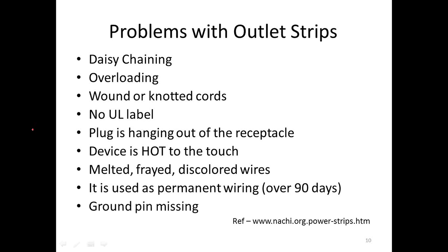Melted, frayed, or discolored wires. Nobody is looking at these things, so they're usually laying on the floor. People walk on them, step on them, put the legs of tables on them, tear them up in all sorts of ways, and nobody is assigned to be vigilant over them to correct problems. They do get used as permanent wiring—we all know once they're in, they're in forever. Nobody ever takes them out. The reason you put them in does not go away, so they leave them there. And obviously you can have a ground pin missing and an ungrounded situation simply because nobody's testing it.